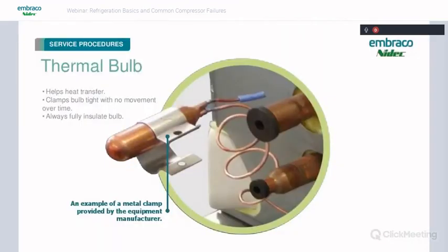And always use the clamp that comes with that bulb. You want to have a very firm clamping between the bulb and the suction line. And if you got a dirty suction line, sand it down, get some nice clean copper. We want good transfer of heat between the bulb and the suction line. And you always want to fully insulate that bulb, because we only want to read the temperature of that suction line, not ambient temperature.